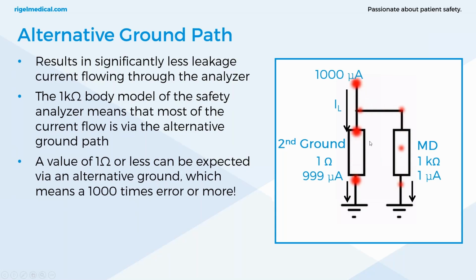And again, if we talk about the 1 kilo ohm body and a value of 1 ohm or less, then if we look at the example in this image, comparing to the 1 k ohm resistance of the body model, the secondary earth ground is, okay, we've given it an arbitrary value of 1 ohm in this instance. Values are much less than can be expected via an alternative earth path. And that means you're going to get errors of 1,000 times or more. It's a significant jump. Again, though, these types of issues are detected automatically by our safety analyzers, and they have a warning if a secondary ground path is detected.